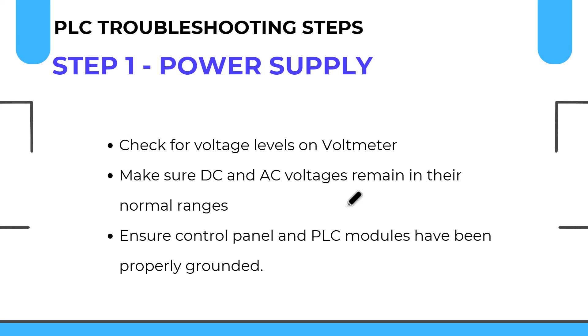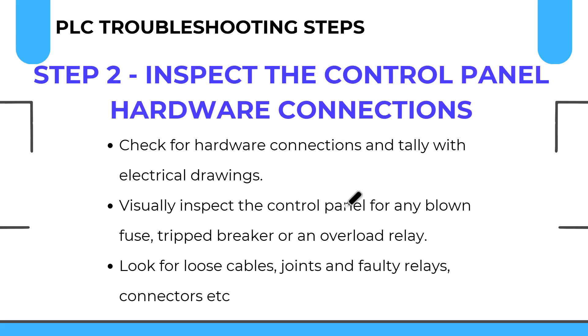For example, the CPU 315-2 DP should be receiving 24V from the power supply module. The digital input, digital output, analog input, and analog output cards must all be taking proper power from the power supply module. You can check voltage levels with a voltmeter — DC voltage should be within the normal range, as should AC voltage. The power supply must have a proper earth connection and the PLC panel must be properly grounded.